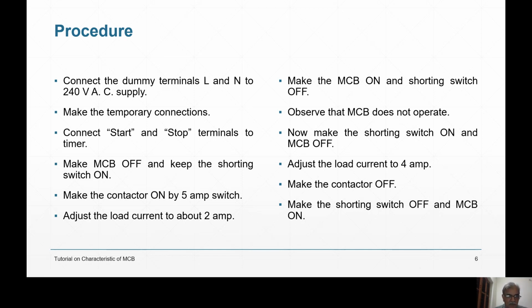But I know that my MCB insulation is going to be damaged, or my equipment is going to be damaged, if the temperature reaches 60 degrees. So I should see to it that it does not reach 60 degrees. But now try to understand that if you are starting the MCB fresh, it has to go from 30 degrees room temperature to 60, the damaging temperature. But if it is running for the last 2 days, then it has to start from 45 or 50 degrees to 60. So obviously, if the MCB is under hot condition, already under working condition, then the time taken to trip the MCB is less. And if it is not under working condition, you are starting fresh, then the time taken will be large for the same overload.